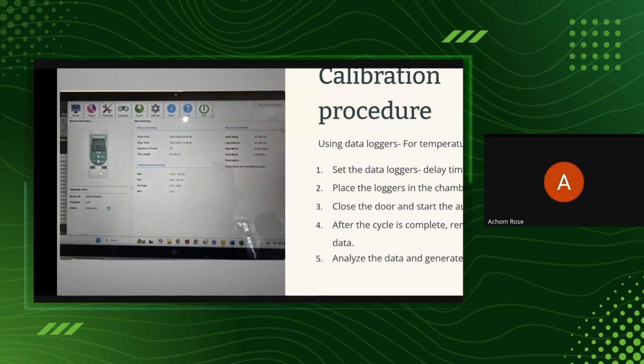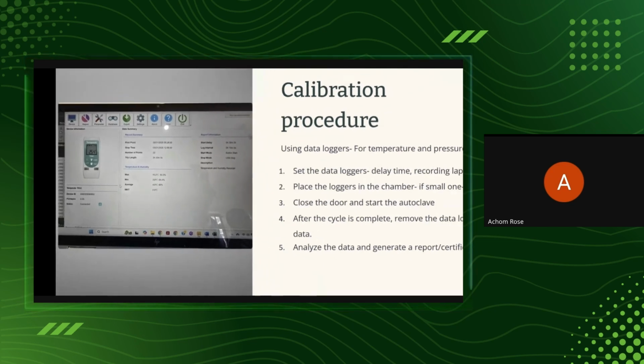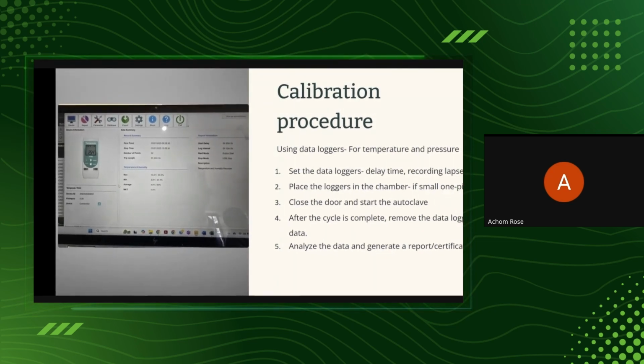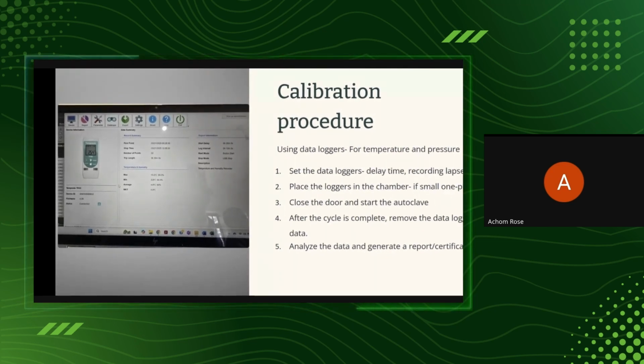And then you know that let me have a logger at the top, I have a logger in the middle, and I have a logger at the bottom for the top loading. And then for the horizontal loading, you may decide to have a logger maybe at the right, a logger in the middle, and a logger at the back. Then afterwards, you start the autoclave. Okay, but if it is a small one, you can just have one logger and place it in the middle. Then you close the door and start the autoclave.